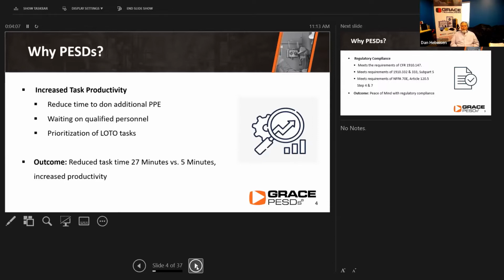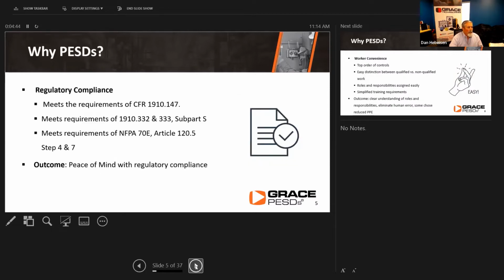And it gives us the prioritization of where our most hazardous locations are, how frequently we are doing these lockout tagout procedures, and what our exposure is. And then probably the most important is that by adding these types of devices, we're able to speed the lockout tagout procedure, which some customers have told us they've reduced their task time from as much as 27 minutes down to 5 minutes. So obviously that is a great payback on the productivity. And the main thing is we're continuing to keep people safe in that environment.